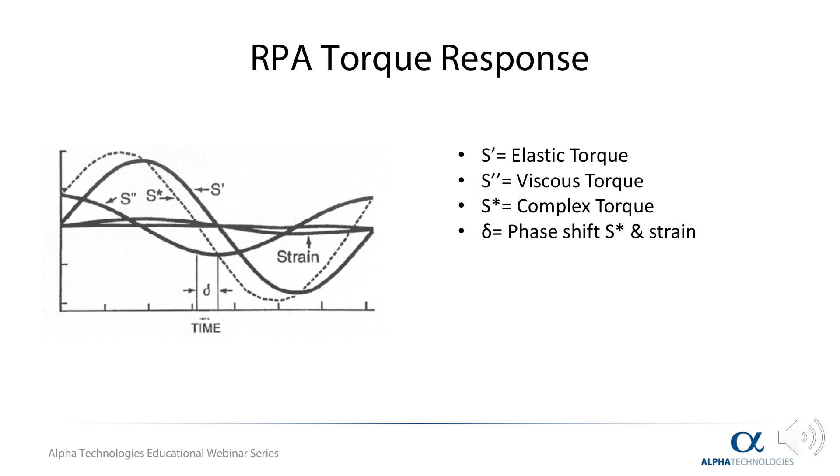The RPA functions by applying a given strain at a given frequency to an enclosed sample and then measuring the torque response of the material. The dashed curve above displays the torque response. This is the property the instrument directly measures and records.